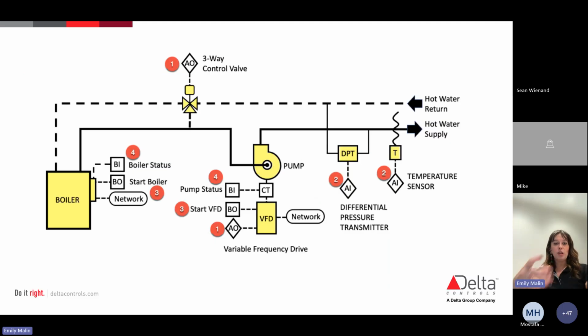So when we look at this, it's again the same type, it's just a little bit better of a schematic than our last one. It's a little less rudimentary. But what I like about this one, and where we are really starting to focus, is we're starting to see a lot of these inputs and outputs, right? So when we think about our mechanical equipment in general, we want to take our zone, we want to take that system from a set point of 65, and right now it's being measured at 55. So how do we get there? And the reason I like this slide too is that you guys can see what our inputs are going to be, what our outputs are going to be, and what we need to start focusing on in order to make sure that we are getting that desired temperature in our space.